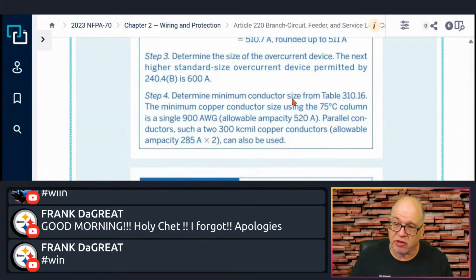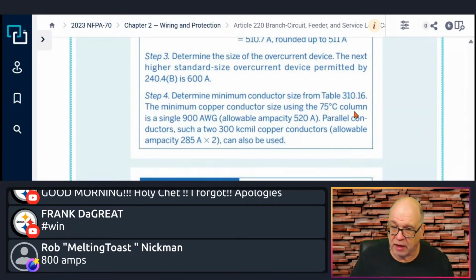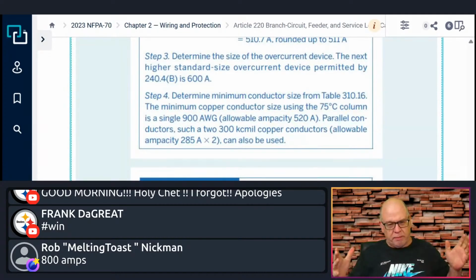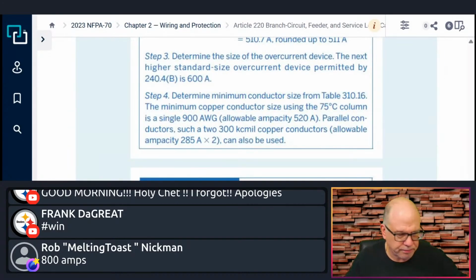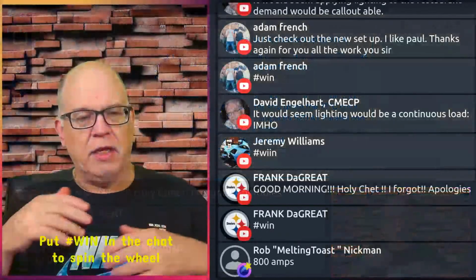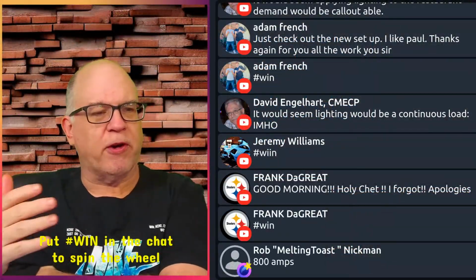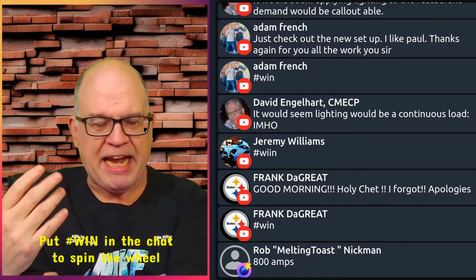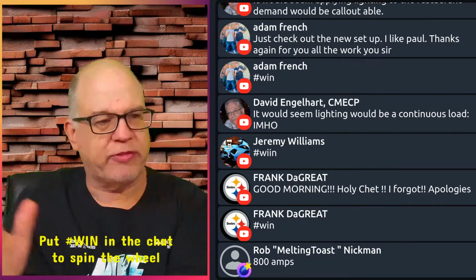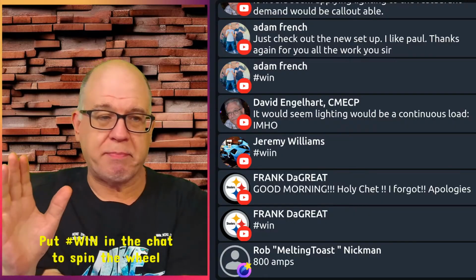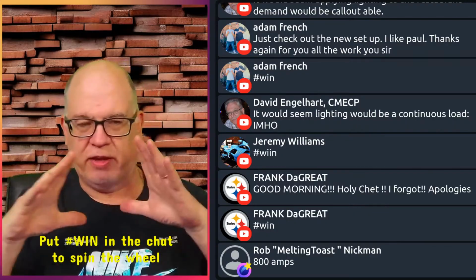Now, determine the minimum conductor size from Table 310.16. The minimum copper conductor size using the 75 degrees C column is a single 900 kcmil, which has an ampacity of 520. And this is another important thing, people ask me, when do I know how to parallel? Always look at what it would be for a single conductor. And reality is nobody wants to run 900s. Nobody wants to try to bend it. It's just not going to work.